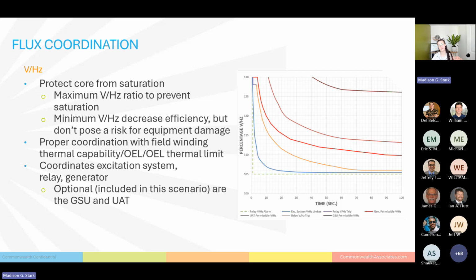This particular example has some additional elements that are coordinated for and planned for, which are the UAT, the unit auxiliary transformer, and then the GSU, which is the generator step-up transformer. This is what connects the generator to the grid, and this is what provides power to the generator equipment. So your relays and your exciter and all of these things are powered by the unit auxiliary transformer. So great things to protect for, especially in the event that one of them had a lower flux tolerance than the generator. This would be a great thing to show coordination for. However, it is not required. Great thing to do, not required.